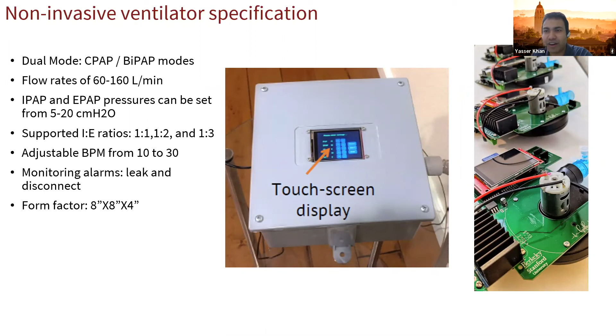We made 5 units for the first batch. 4 of them are in Bangladesh. 1 is in Bolivia. They are now going into a clinical trial. I'll show the results. And we also checked the pressure and flow reproducibility. So here I'm showing the 5 devices, basically what, this is the pressure you set, 5 centimeters of water pressure, 10 and 15. We essentially get a really good batch to batch reproducibility.